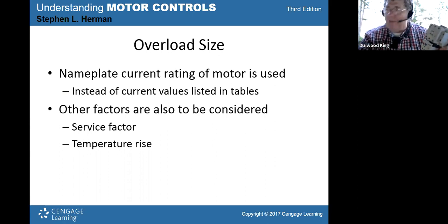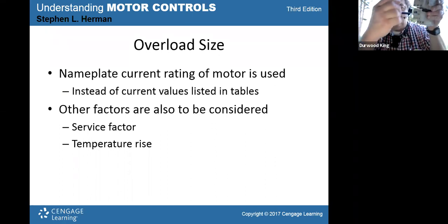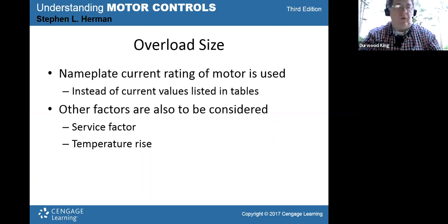If the nameplate amps said what the chart did, and it's going to be close to it, you get the actual full load amps off of the nameplate and multiply it by 1.25, and it's going to give you the setting for that overload. And that's what you dial that into, so that the starter would trip out safely.